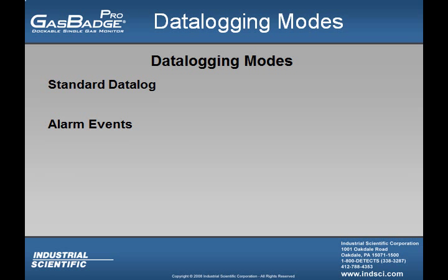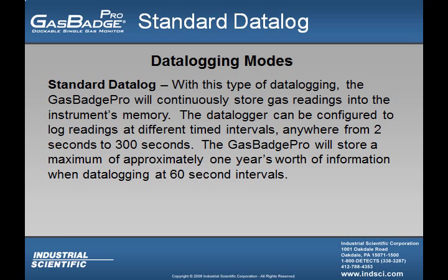Available in the Gas Badge Pro are two data logging modes: standard data logging and alarm events. With standard data logging, the Gas Badge Pro will continuously store gas readings into the instrument's memory. The data logger can be configured to log readings at different timed intervals, anywhere from 2 to 300 seconds. The Gas Badge Pro will store a maximum of approximately one year's worth of information when data logging at 60-second intervals.